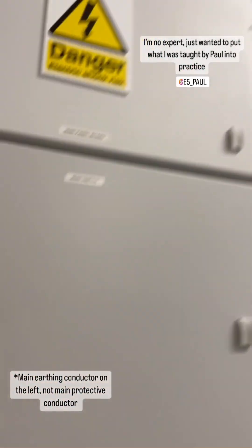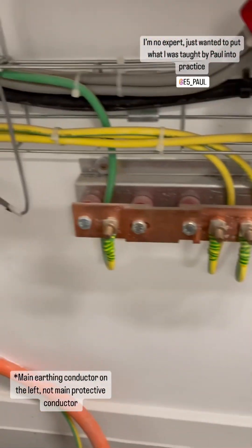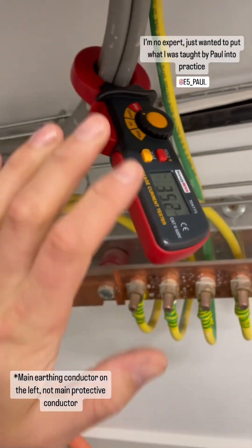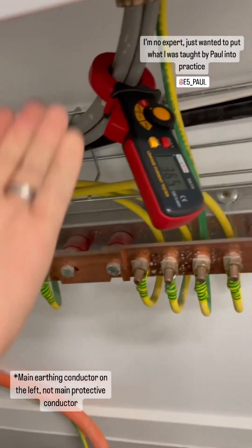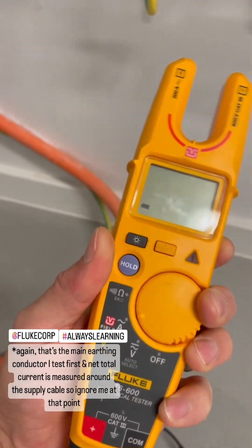We have our 100 amp isolator — main earthing conductor, gas, water — that goes up to the sub panel which does all the consuming in this place. Currently it's reading 30-something milliamps across the whole installation, which is really good natural leakage you'd get from various final circuits and accessories connected.